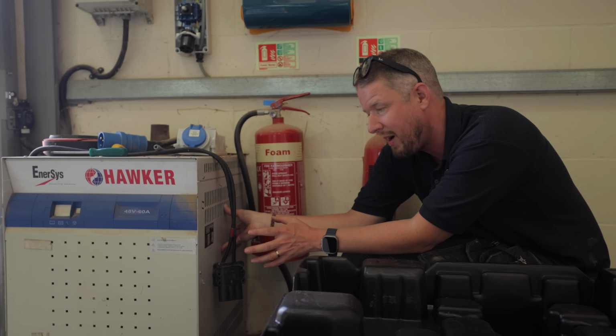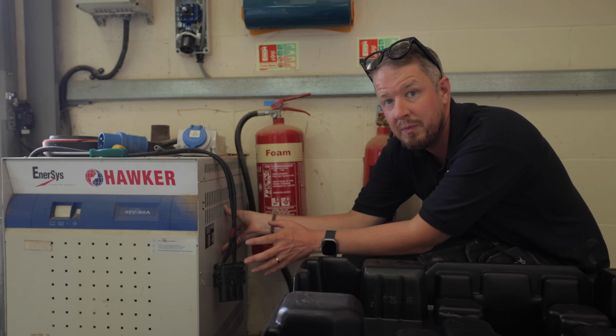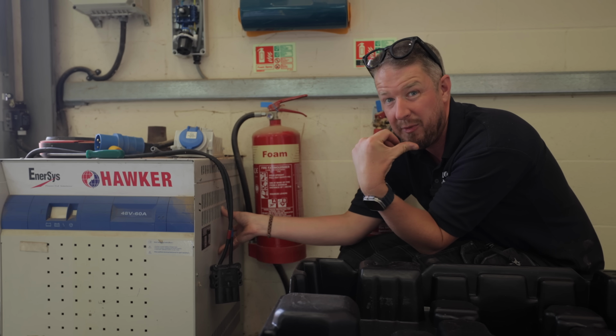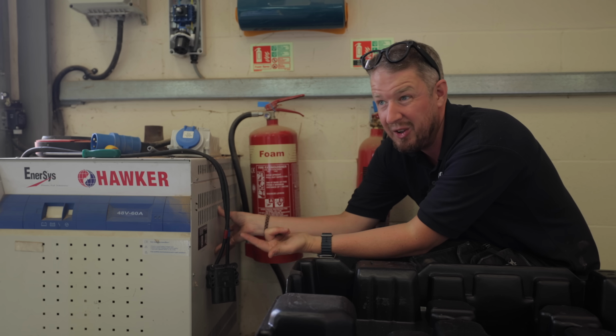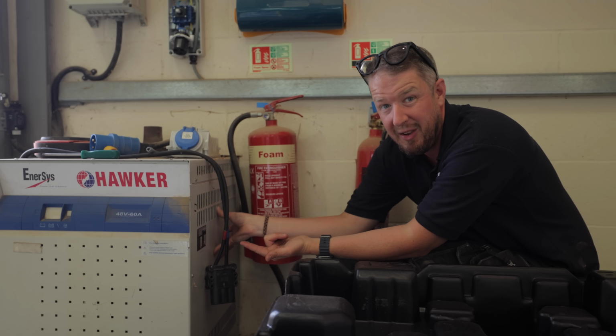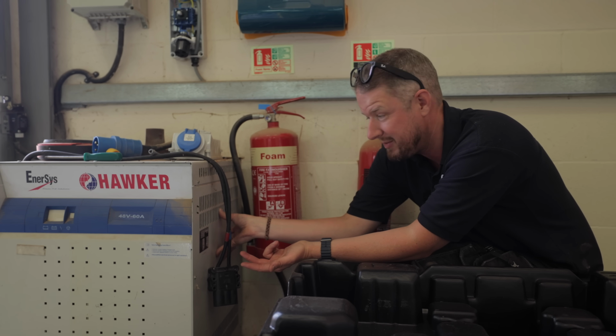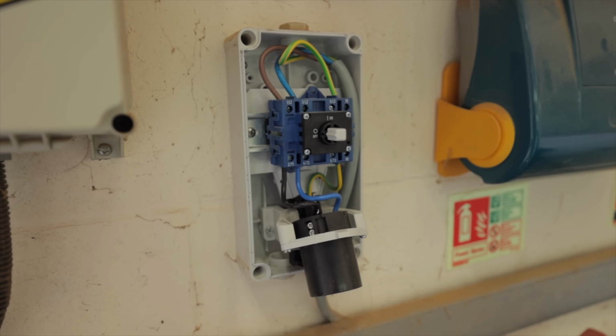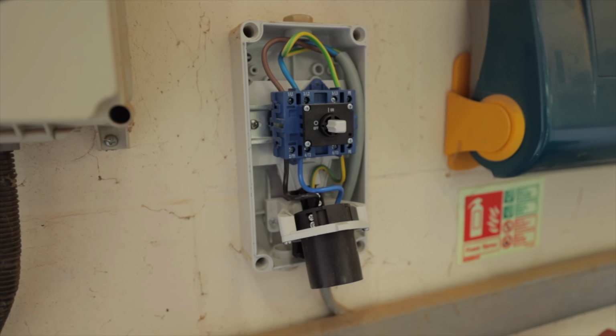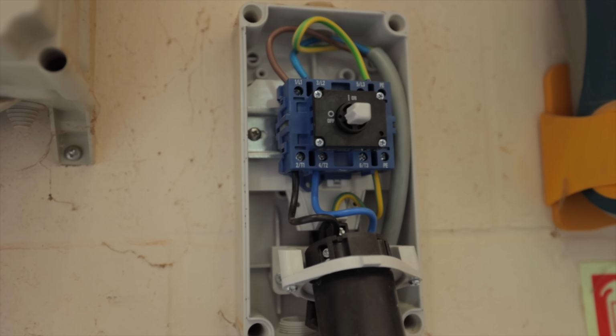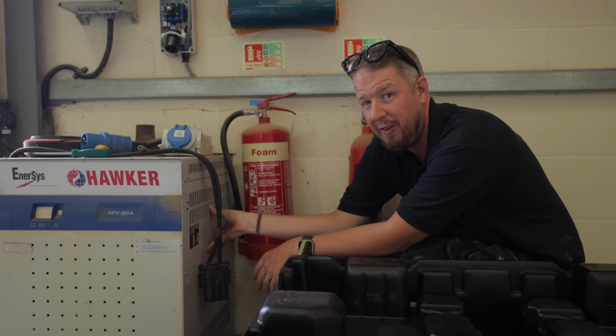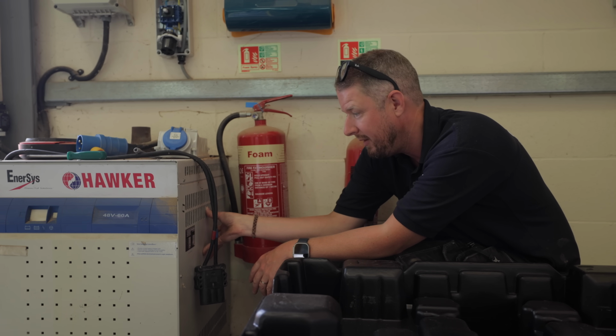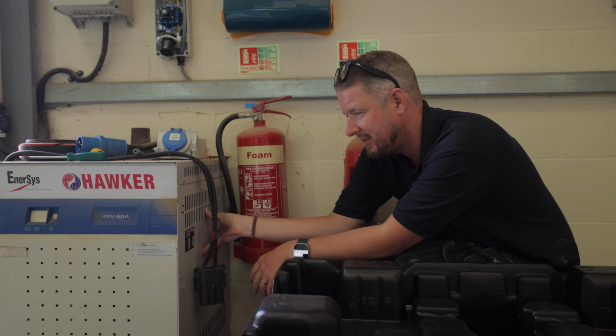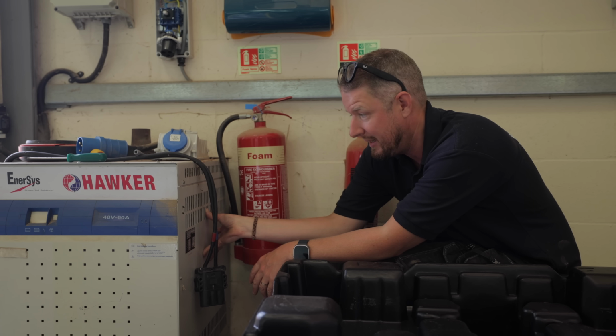It actually says the rated amps is 21 amps, so I don't know why they've put it on a 40 amp circuit breaker. It could be on a 32 amp or a 25 amp circuit breaker. I'd probably put it on a 32, as it's got a 32 amp commando socket for it, but it's on the edge.